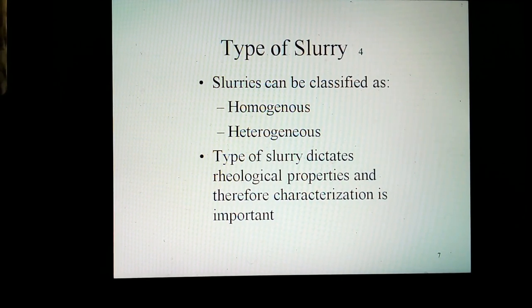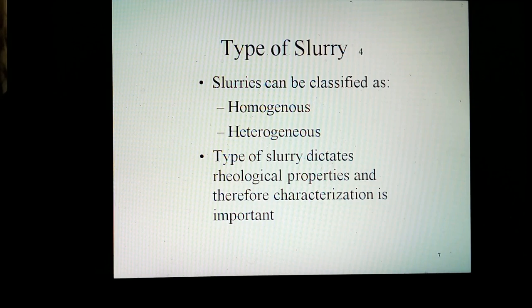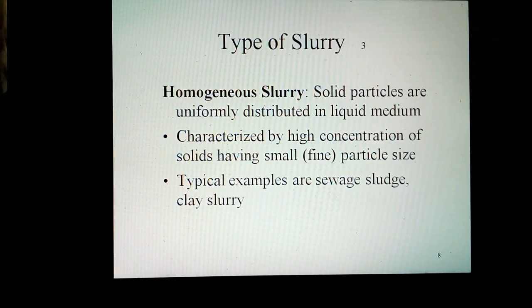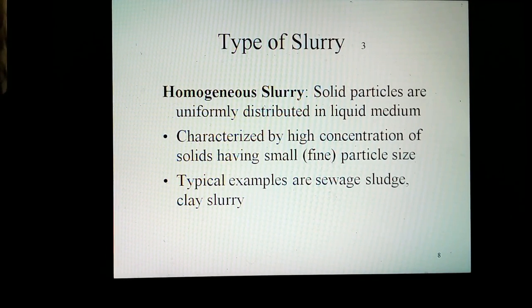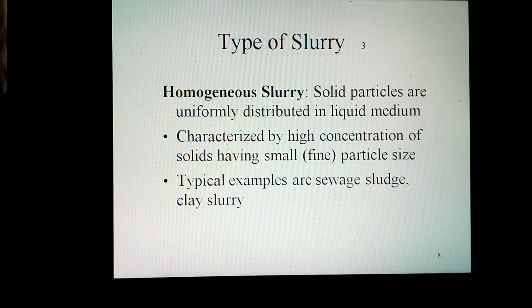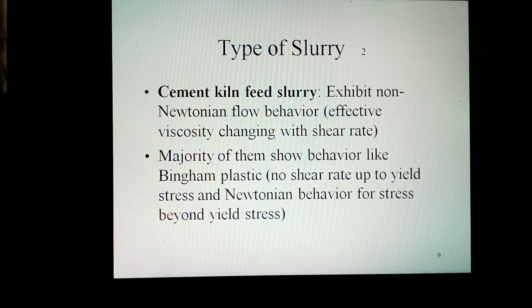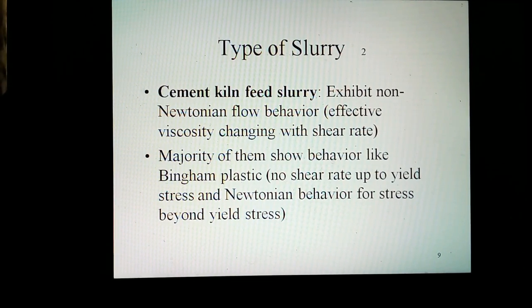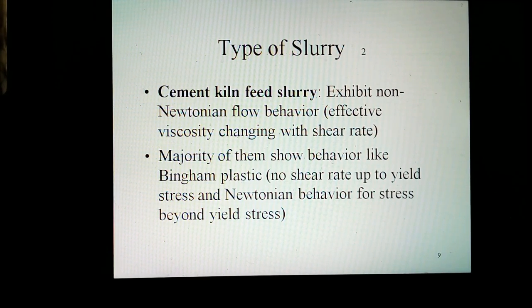Slurry can be classified into broad categories as homogeneous or heterogeneous. The type of slurry — whether homogeneous or heterogeneous — dictates rheological properties, and their characterization is important. In homogeneous slurry, solid particles are uniformly distributed in the liquid medium. Such slurries are characterized by high concentration of solids having small, fine particle size. Typical examples are sewage sludge, clay slurry, and cement slurry. Such slurries usually exhibit non-Newtonian flow behavior, with effective viscosity changing with shear rate. The majority show behavior like Bingham plastic — no shear rate up to yield stress, and Newtonian behavior for stress beyond yield stress.